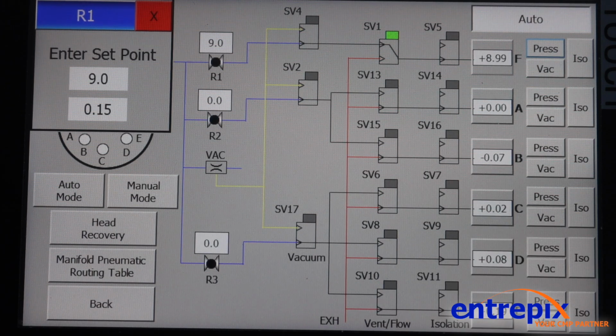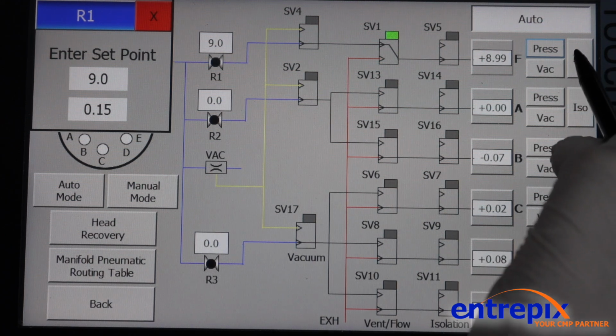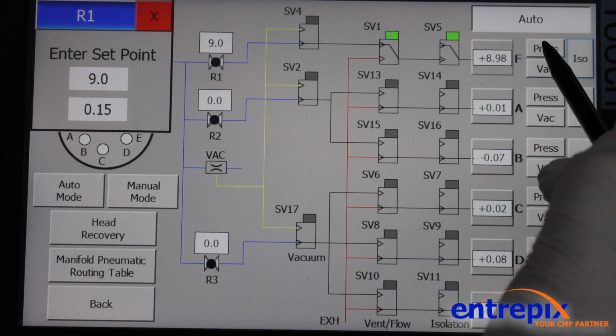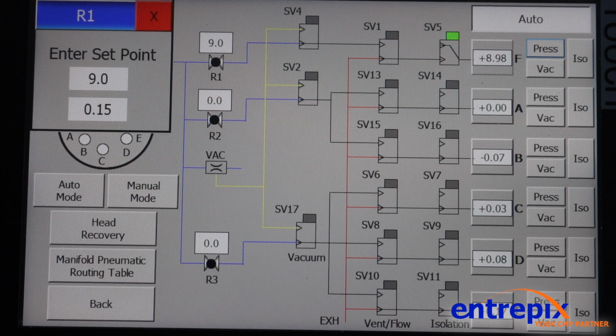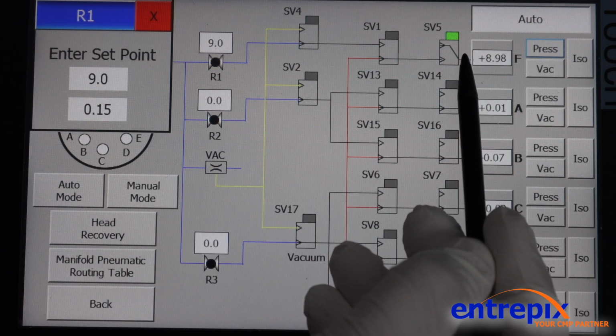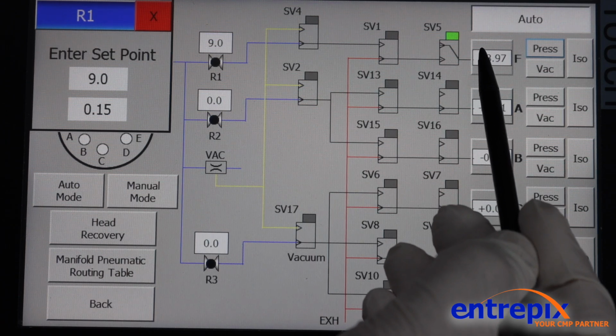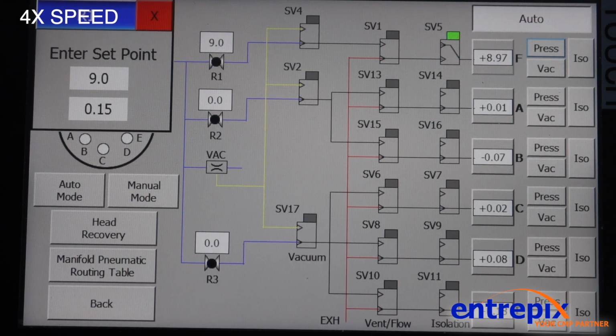In order to test for leaks within the zone, select the isolation button. You'll see upon selection of the isolation that the valve becomes live, and then we can turn off the supply pressure by depressing pressure again. The pressure is now captured in the retaining ring zone of the head, and we can watch the transducer feedback over the duration of 30 seconds and monitor for a leak. As you can see, after the duration of 30 seconds, the transducer indicates that the chamber is holding pressure, with a very small, if negligible, leak indicated.